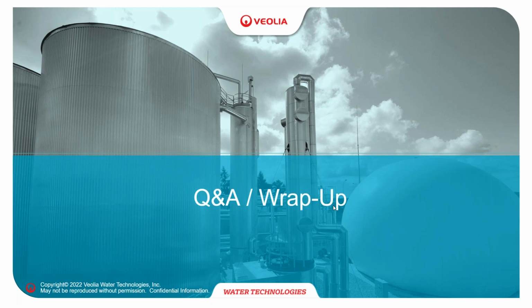Hopefully you can collect condensation from any points that are above ground. There's probably a way to clear out the lines periodically, but it would require more equipment and possibly isolating the system. But you'd want to make sure that you have traps installed at the areas that are above ground and accessible, so that you can remove as much as possible from the system from the accessible areas and prevent having to do more complicated maintenance, would be my suggestion.